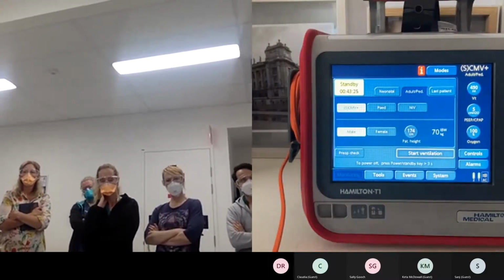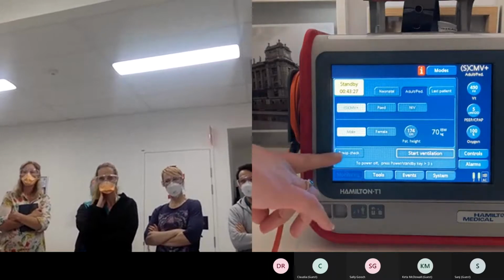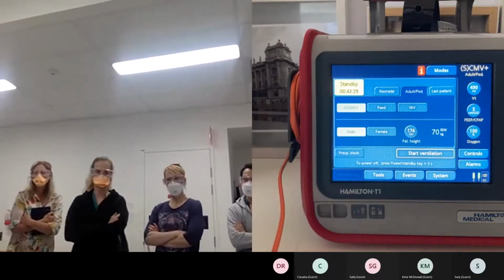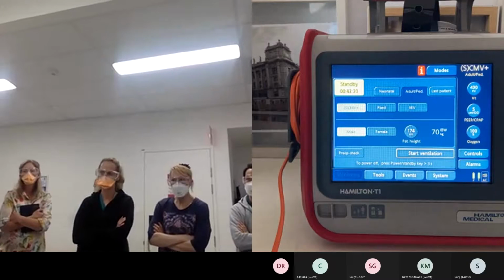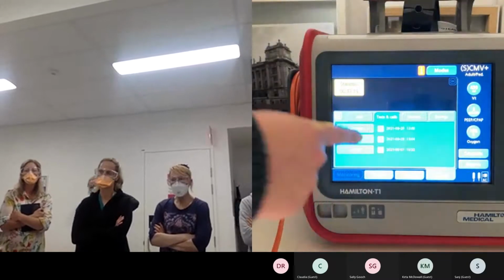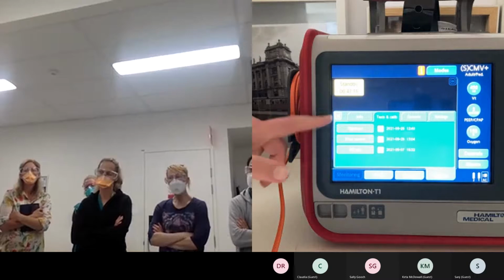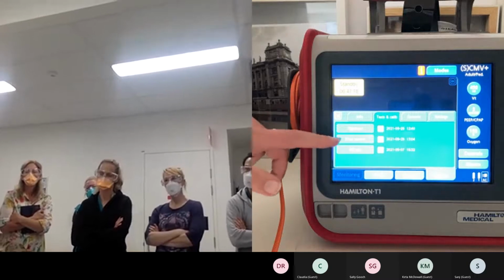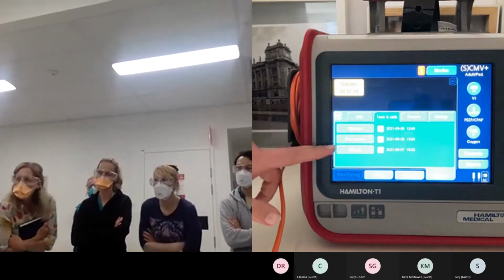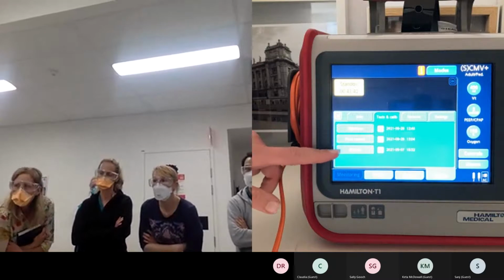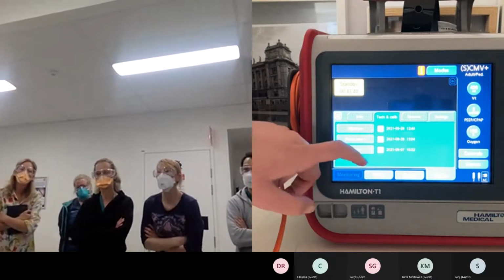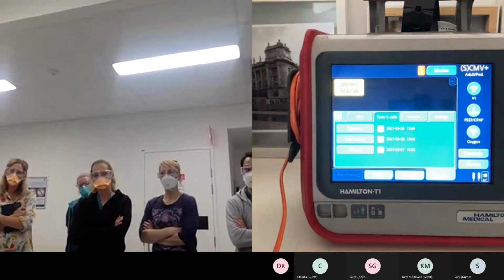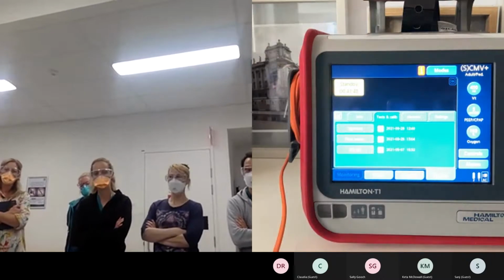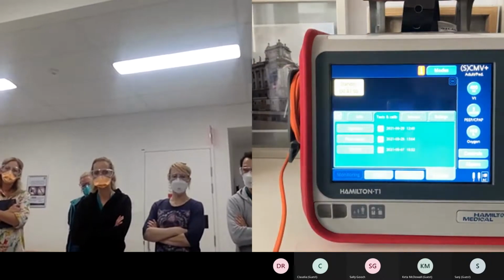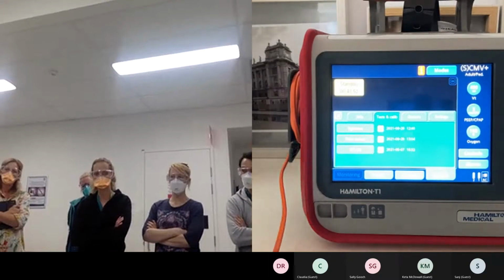So when you look at the screen, down the bottom here, we've got a button that says pre-op check. So the screen always starts up in this view. So you touch on pre-op check, and you can see that there's 3 checks here. So the top one is tightness, flow sensor, and O2 cell. With the O2 cell, you would only need to do it if it came up with a red cross, at which point you just double check you're connected into your oxygen, and then you would just touch on it to run it.